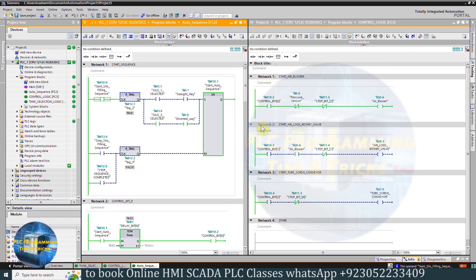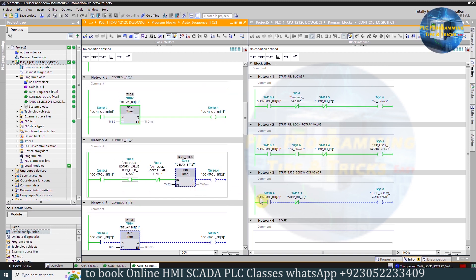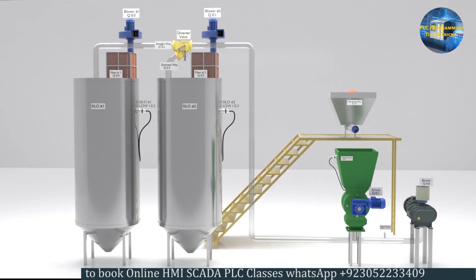In the control logic function, as control bit 0 turns on, it turns on the air blower output Q0.6. After a 5-second delay, control bit 1 turns on and this turns on the rotary air lock valve Q0.7. In Network 3, after another 5-second delay, control bit 2 turns on and it turns on the tube screw conveyor Q1.0. Material now starts to transfer towards silo 2.